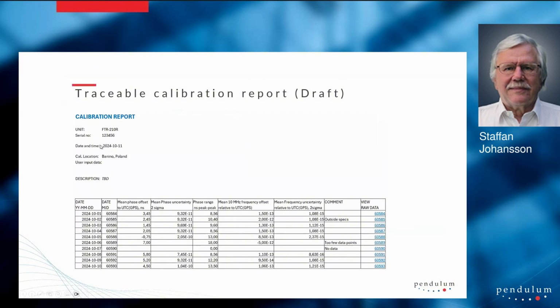We can produce a traceability report, and this is a draft version of it, and it will contain the day-by-day phase offset, average phase offset data to UTC with uncertainty, also the peak-to-peak variations of the 1 PPS during the day, the average 10 megahertz frequency offset to UTC with uncertainty, comments if you're outside specs or if you have too few data points during the day to make a reasonable uncertainty calculation, or if there is no data at all.